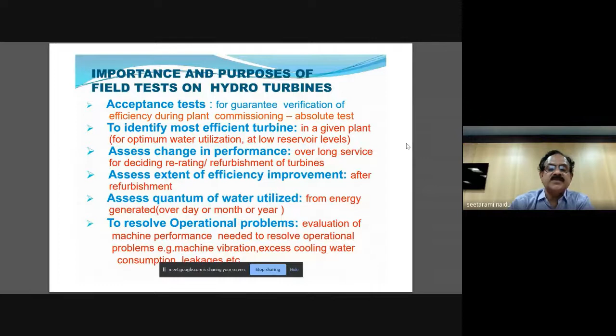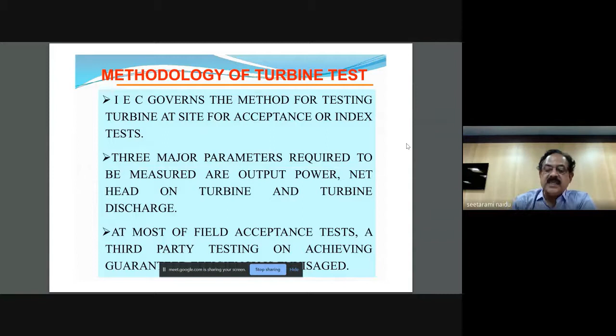IEC 41 governs the method for testing turbines at site for acceptance or index tests. Three major parameters required to be measured are output power, net head on the turbine, and turbine discharge. Power is easy, head is also easy, but discharge is always a challenge to measure.